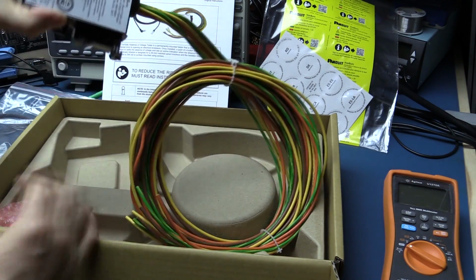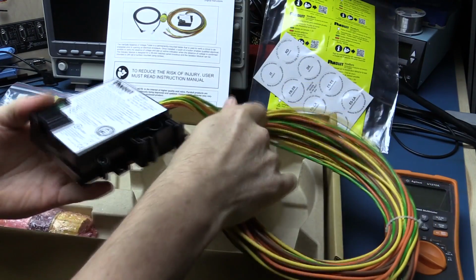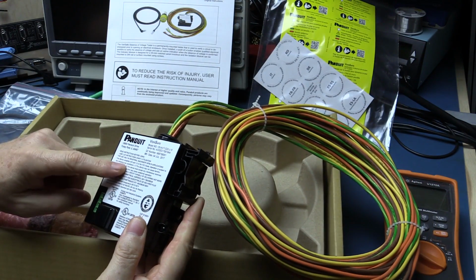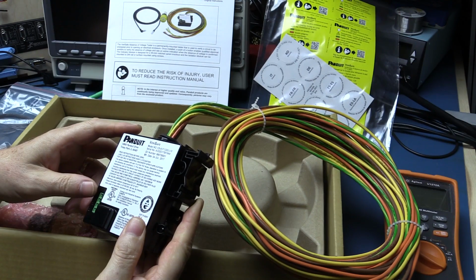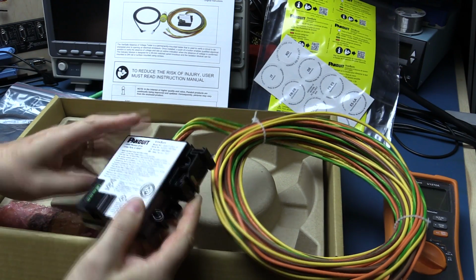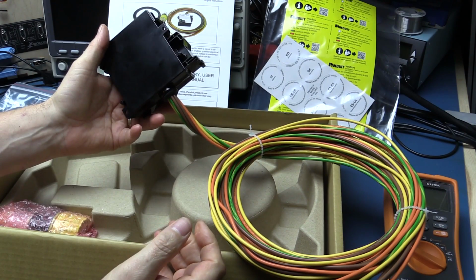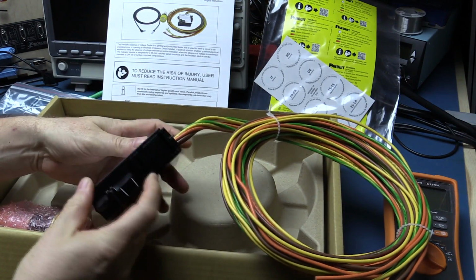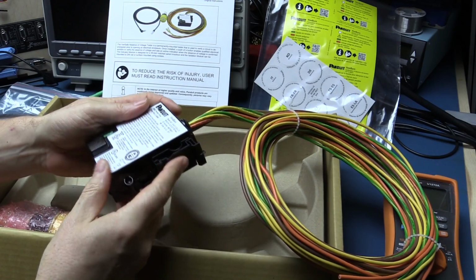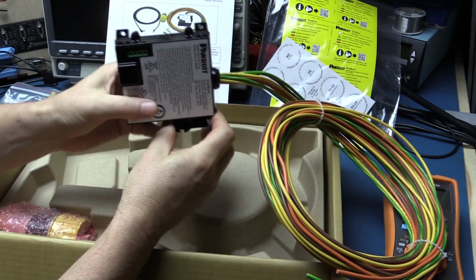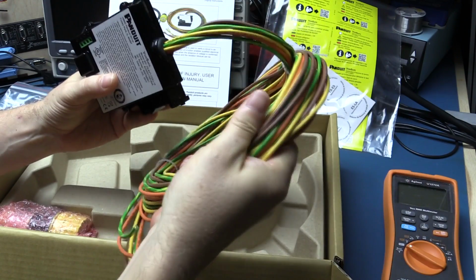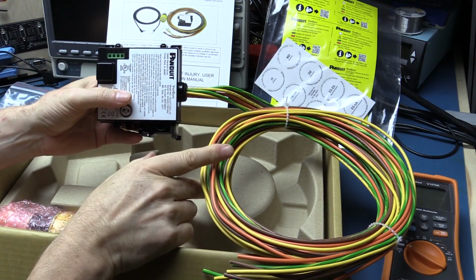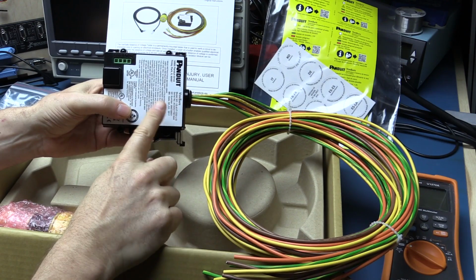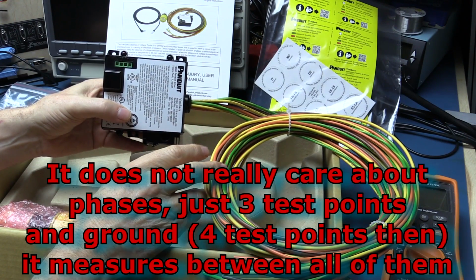So we have the actual testing unit with a whole bunch of pre-wired leads. This is the Verisafe model number VSAVT-CO2L10. I don't know what other models there are, but this one is designed for one DIN rail mounting. You can see here it would sit like that on a DIN rail, pre-wired for measuring up to 3 phases. Now the instructions we'll have a look at, but you can handle a lot of different configurations, whether it's star, delta, 2-phase, 3-phase, single phase, etc.